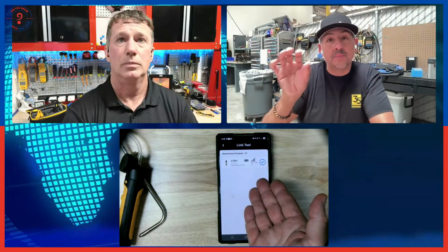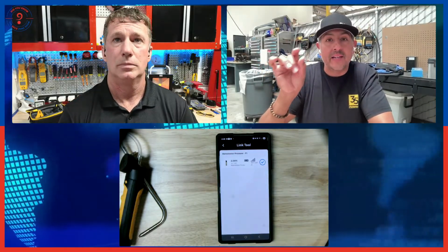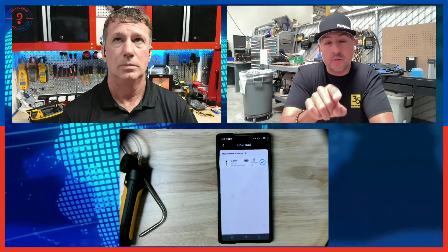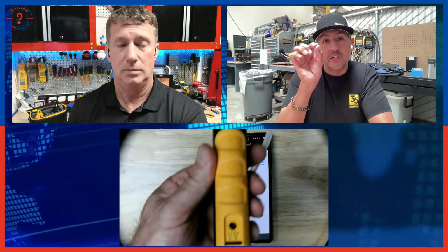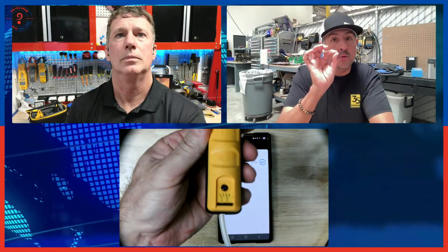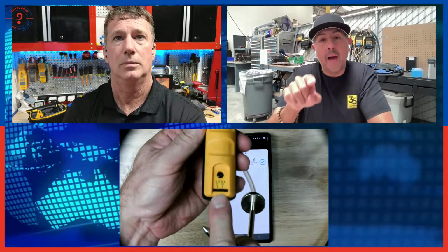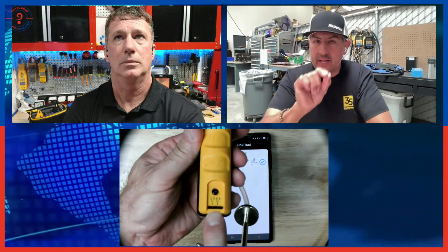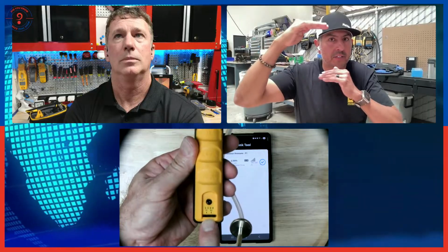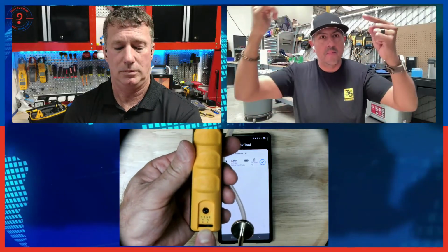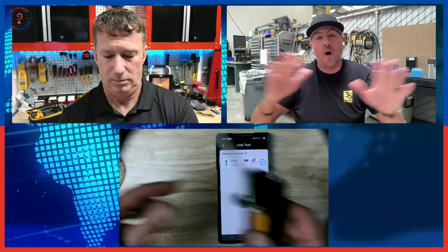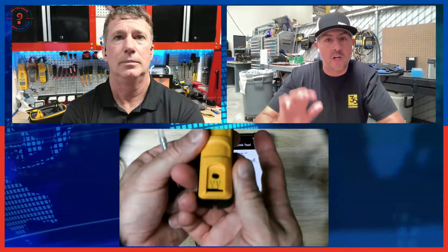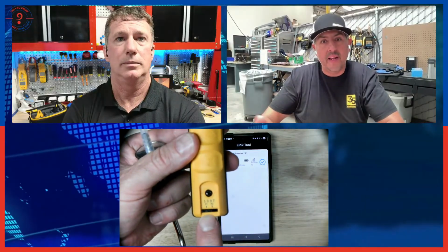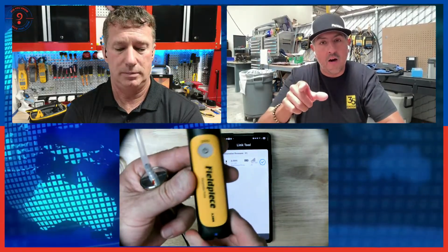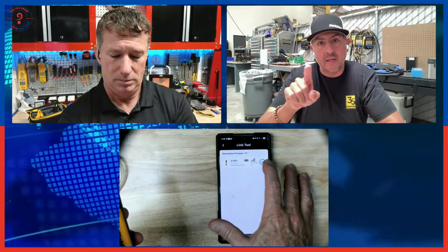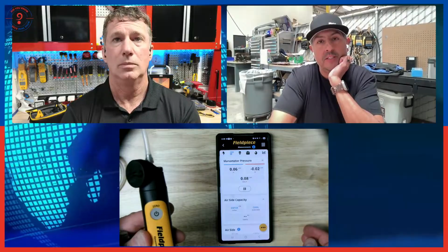It'll display any manometer set to P1. On the back of those probes there's a switch so the app knows if it's your P1 or P2 tool. The app only shows manometers set to P1 when you tap that container, so you don't reverse the reading, and that goes for all the tools. One is set to P1, one to P2, and if it's powered on within range, it'll show there. You just click on the black circle to make it a blue check mark, and that's when you get measurements on your screen.